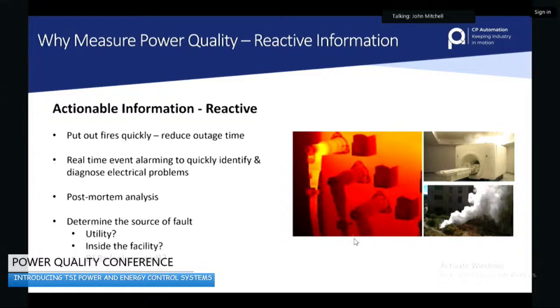So what kind of problems do we have? Basically, most of the time people have power quality problems and it's a reactive issue. What do I mean by that? They've had a failure, a problem, and now they're reacting to it. If you put the meters in, you can register when these things are happening, then put mitigation in and show that those problems have gone away. That in itself is enough that customers don't need to worry, specifically when it comes to root cause analysis.